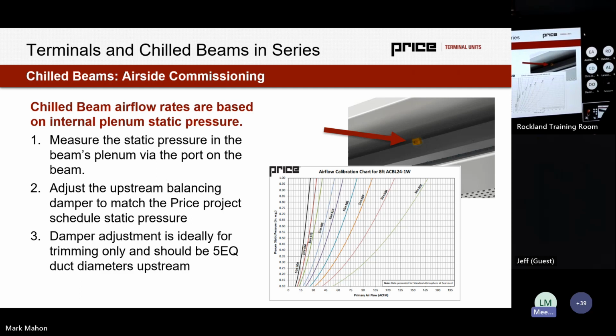So the best thing to do at that point, if we're looking at demand control ventilation and maximum turn down ratios, would be to reach out to the manufacturer. In this case, Chris and Matt would have good metrics on that. I know often a 3-to-1 turn down ratio would be pretty comfortable for a beam.